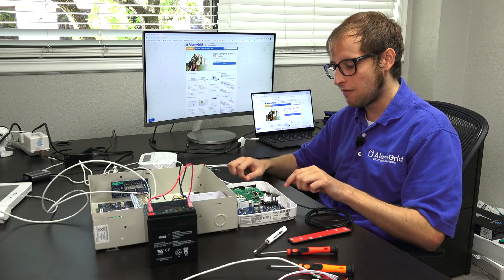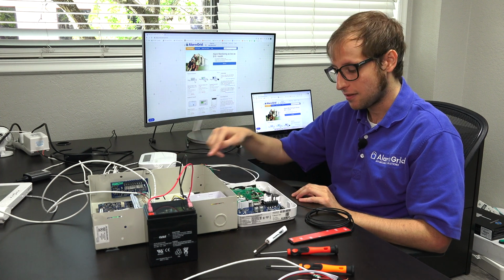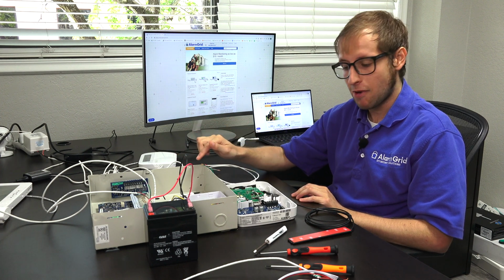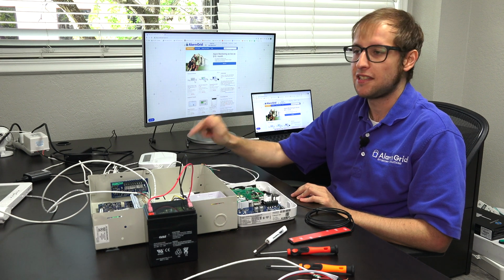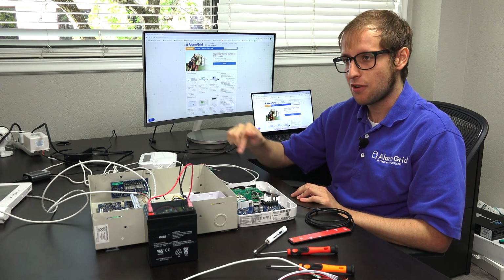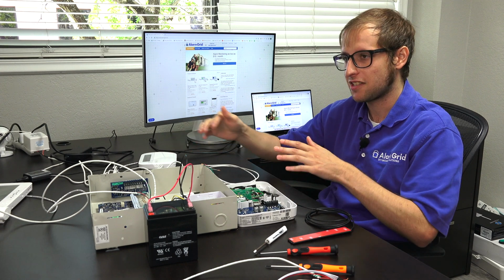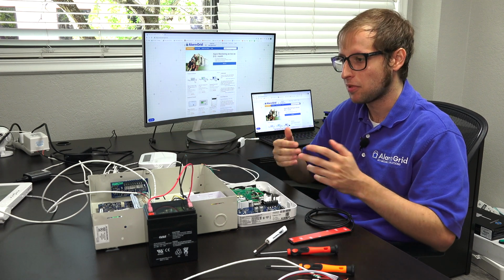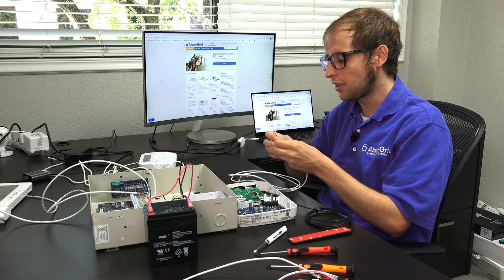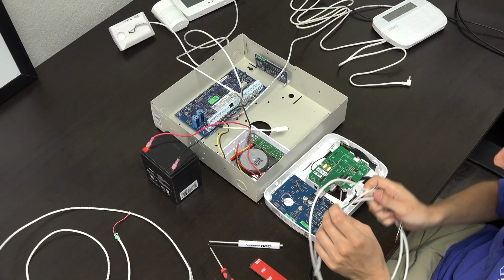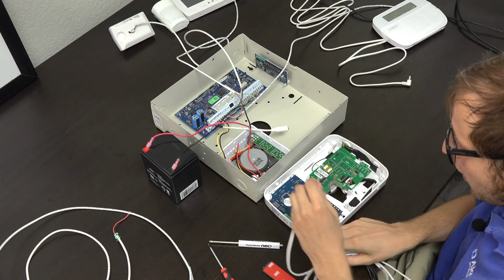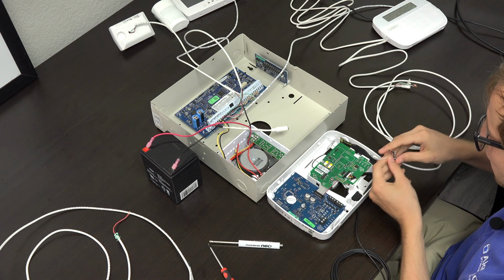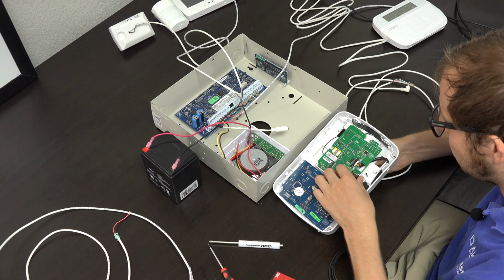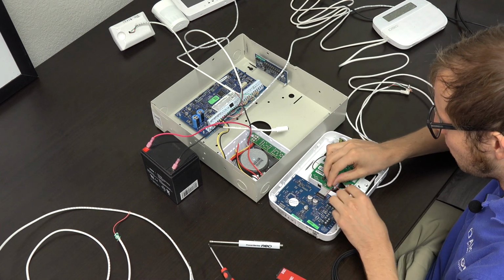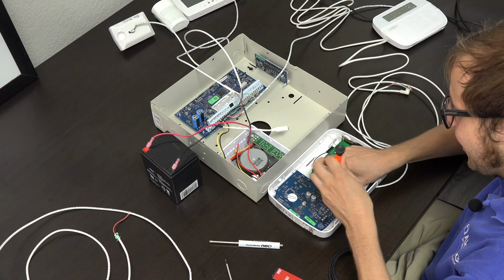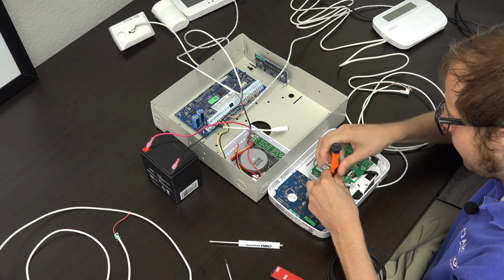So the way this is going to work, we're going to have TX plus going to RX plus, TX minus going to RX minus, RX plus going to TX plus, and RX minus going to TX minus. So match the TXs and the RXs, and then keep the plus and minuses the same. And the color really doesn't matter as long as you remember to match the colors. So we're just going to go randomly here. It's really not important. And remember to run your wires through the backplate, which we're going to do. We're going to stick it through, just like so. And our terminal block is open, so I guess we're starting with the red wire here.